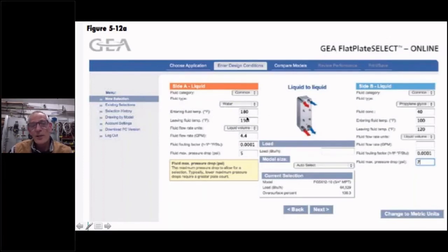So all you need to know is all these different conditions. If you know the temperature on the A side and the B side, you can predict the amount of heat energy that this little plate heat exchanger can move. And you can play around with this. You can change the temperatures on there. You can change the size of the heat exchanger. You can play with different pressure drops if you want to make sure you can do it with a small circulator pump. Basically, you just change the dimensions of the plates or the size of the external dimension of that, and you can really nail these into an exact number.